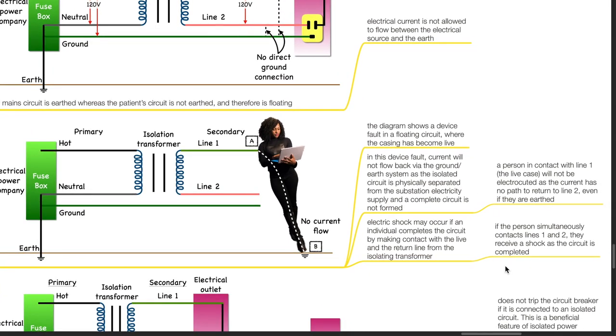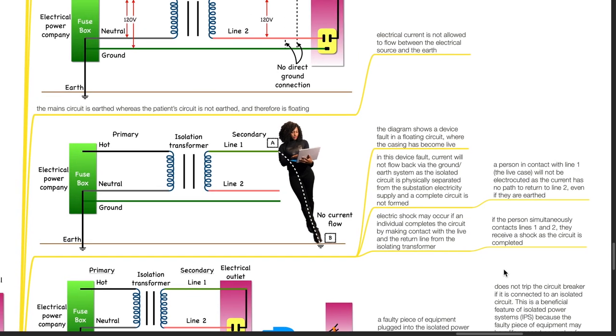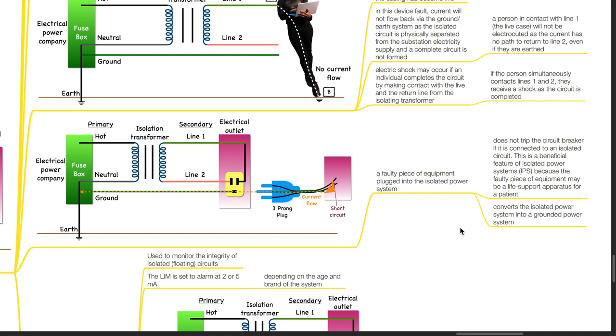The diagram shows a device fault in a floating circuit where the casing has become live. In this device fault, current will not flow back via the ground or earth system as the isolated circuit is physically separated from the substation electricity supply and a complete circuit is not formed. A person in contact with line 1, the live case, will not be electrocuted as the current has no path to return to line 2 even if they are earthed. Electric shock may occur if an individual completes the circuit by making contact with the live and the return line. If the person simultaneously contacts line 1 and 2, they receive a shock as the circuit is completed. A faulty piece of equipment plugged into the isolated power system does not trip the circuit breaker. This is a beneficial feature because the faulty equipment may be life support apparatus. The isolated power system is converted to a grounded power system when this occurs.